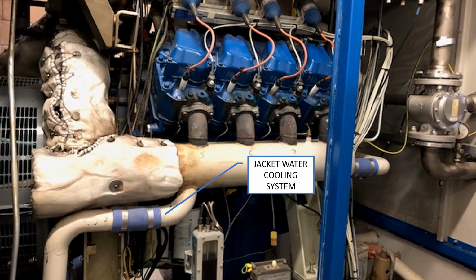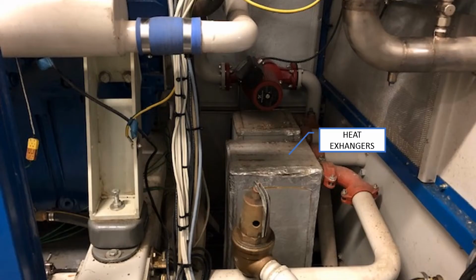In order to keep the engines cool, we run a jacket water cooling system, which is a 50-50 mix of water and glycol. The cooling system is circulating the engine and pulling off all the excess heat and sending it back over to the digester equipment building, where we then utilize that heat to heat up the digestion process. The jacket water system within the cogens goes through a series of heat exchangers. This is where we're taking the heat from the engine, sending it into a mixture that is going back over to the digester equipment building and being utilized for the digestion process.